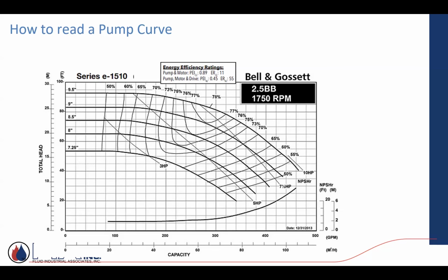There's a lot of information right here in this chart. It's actually quite busy and it can be confusing. But this is not uncommon. This is pretty standard, whether it's in the old catalogs or nowadays online with software. In this particular one, it's a series 1510, a base mounted end suction. This particular size, this 2.5 BB, operating with the 1750 RPM motors. This is the footprint, or this is the DNA. This is the performance capabilities of this model. And it's not just one point, it's several different points.